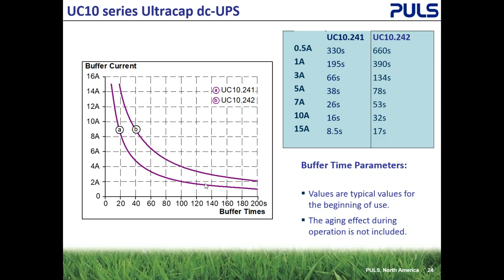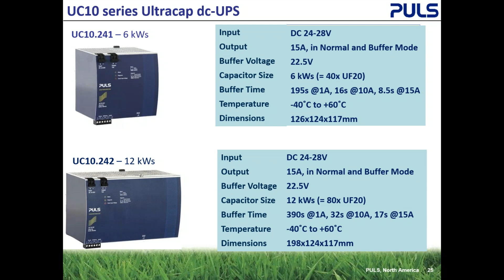Nice thing about this is batteries don't like the cold weather. UltraCaps can operate down to -40, which is great. They can go outside, or inside a metal control cabinet, without having issues with outgassing, because there's no outgassing. These will put out 15 amps. Most people don't need the large amperage output, but they need their runtime, just a couple amps over a minute or so, just to do a shutdown.